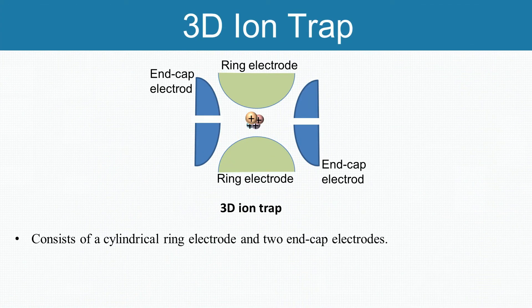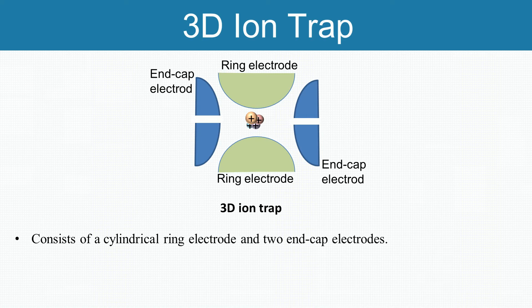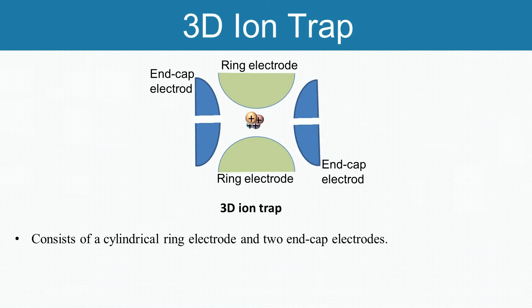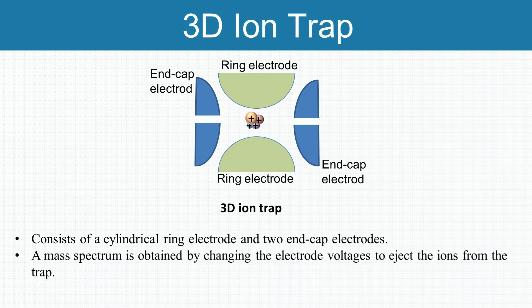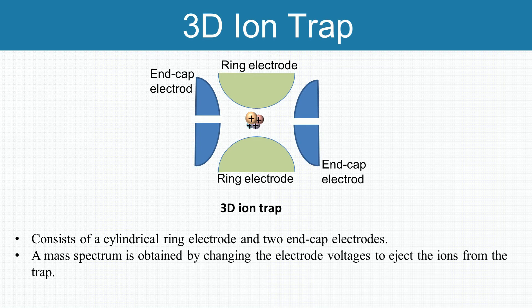The three-dimension ion trap mass analyzer uses three electrodes to trap ions in a small volume. It consists of a cylindrical ring electrode and two end-cap electrodes. A mass spectrum is obtained by changing the electrode voltages to eject the ions from the trap. The end-cap electrodes contain holes for the introduction of ions from an external ion source and for the ejection of ions towards an external detector.